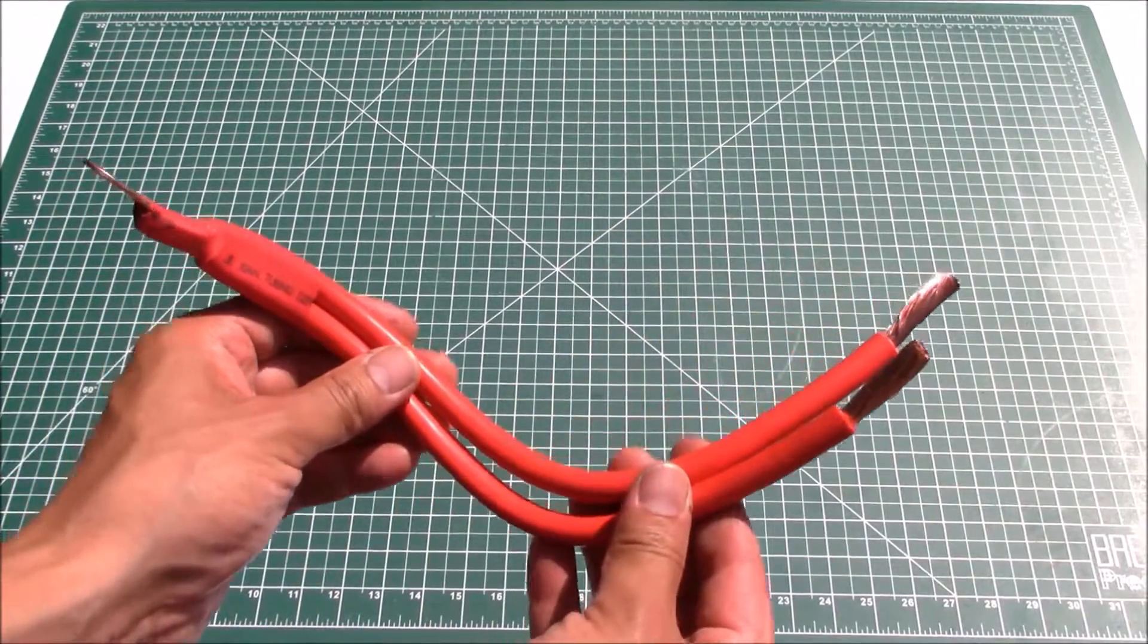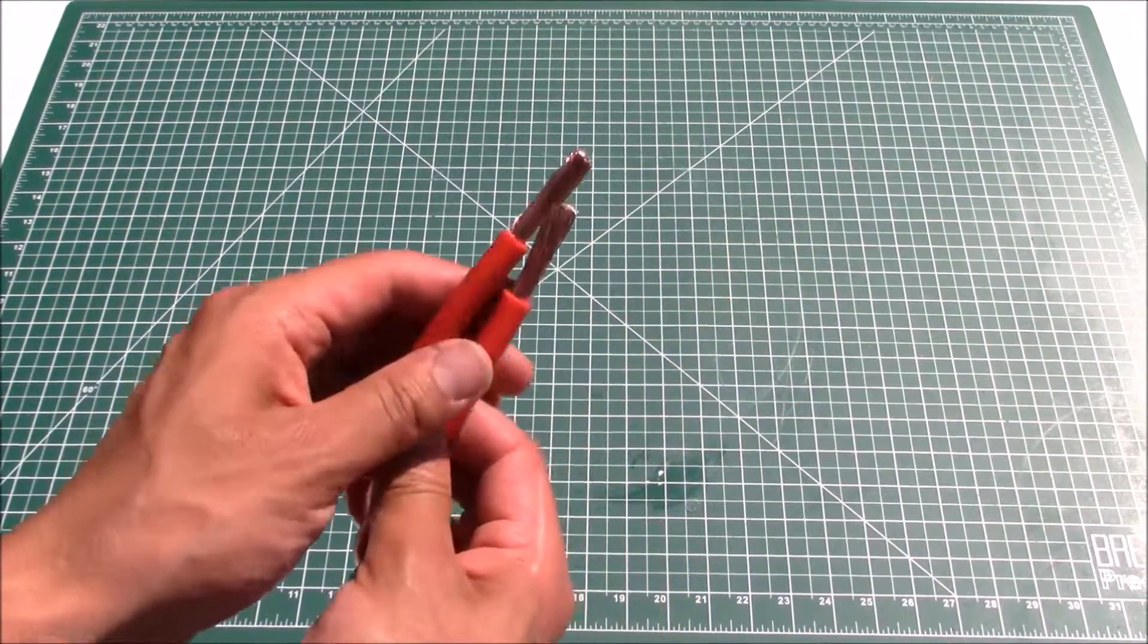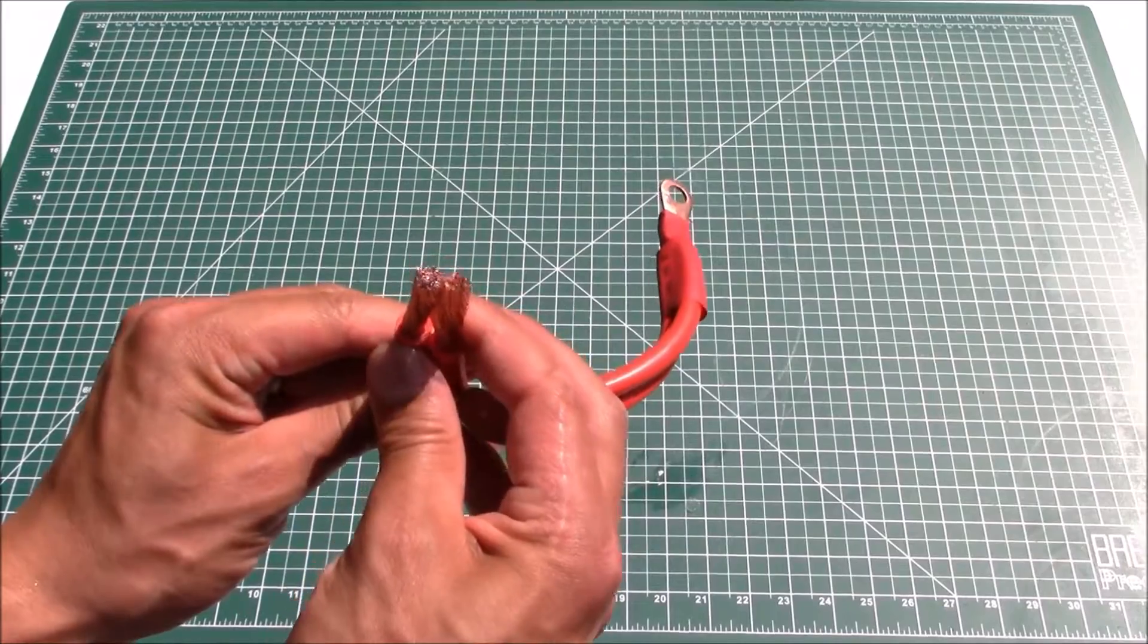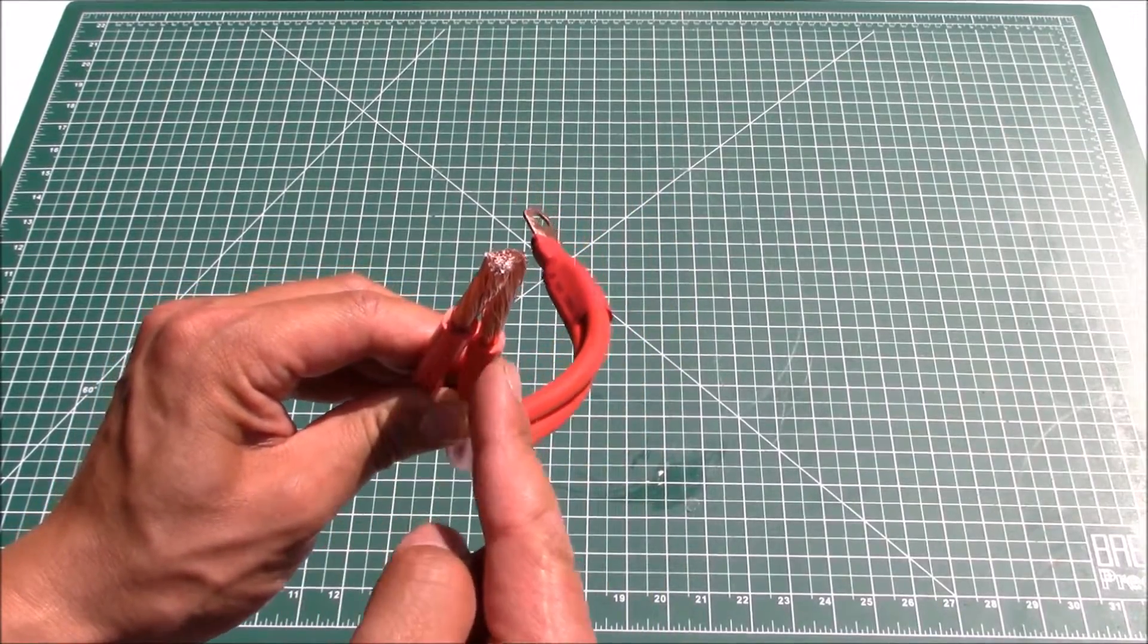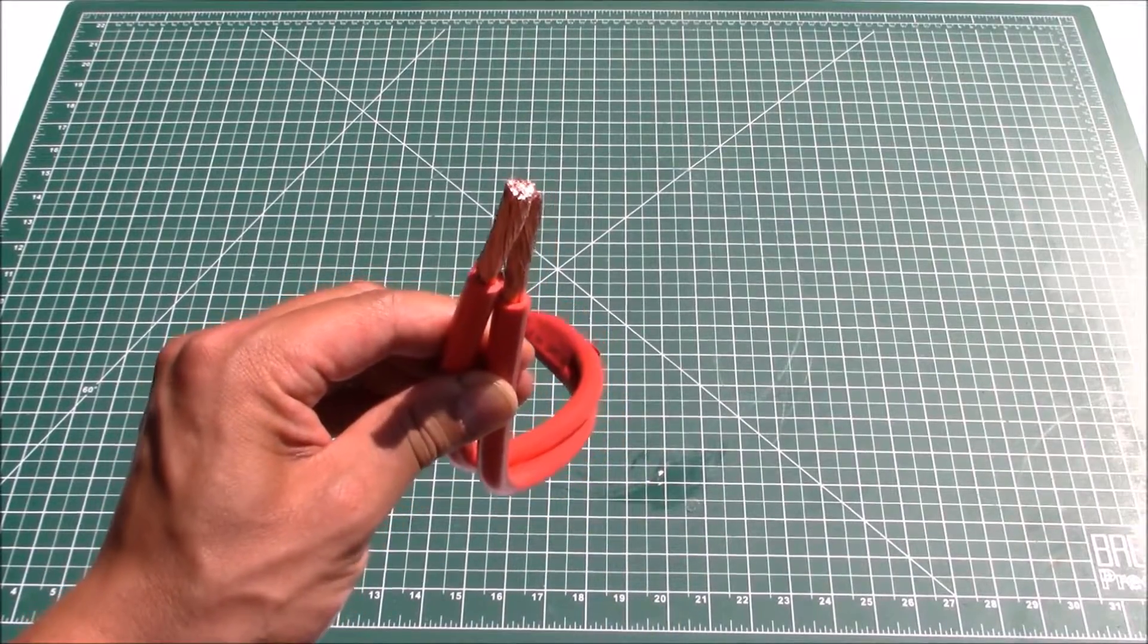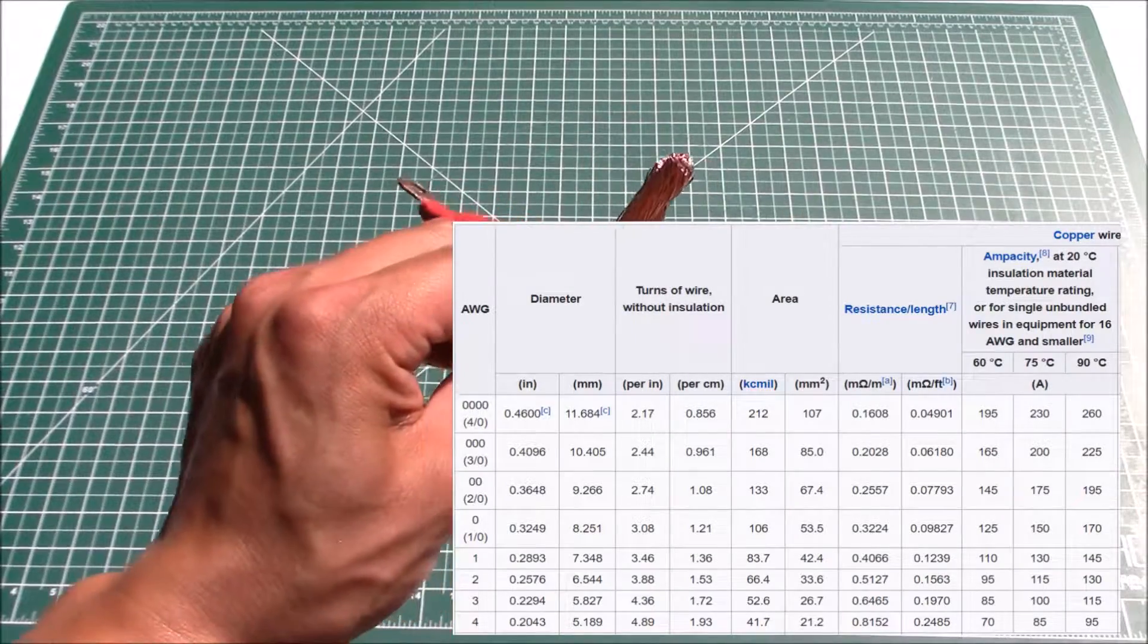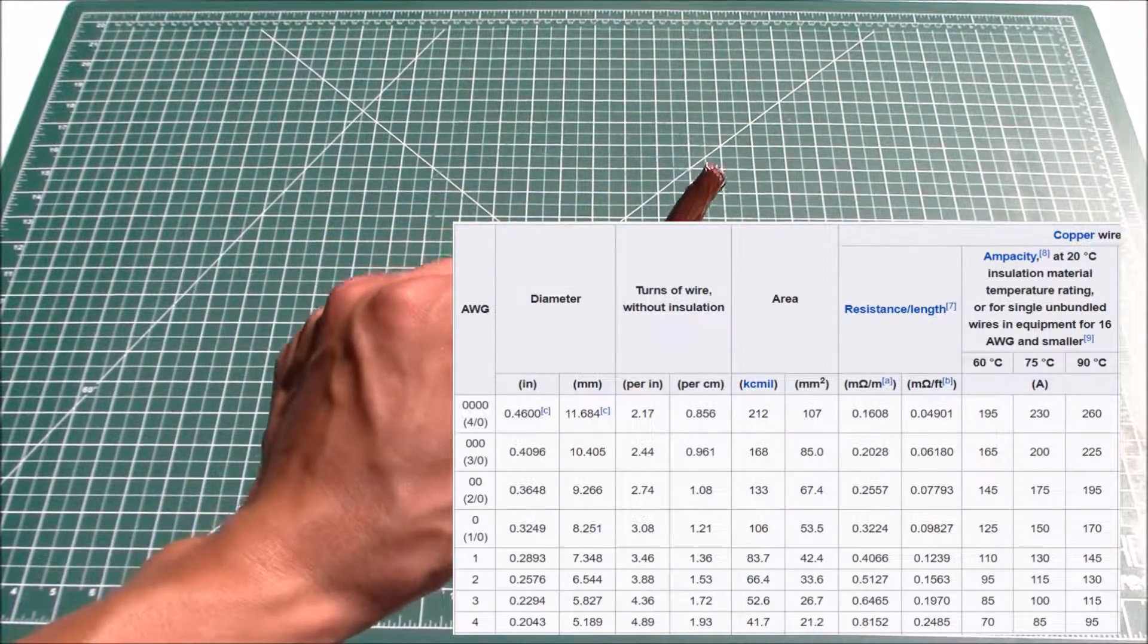The first thing we need to do is identify the nominal cross-sectional area of the cable. Since I've got two of these, you can see the amount of cross-sectional area of these two four gauge wires put together. I did the calculation - it's about 0.0656 inches squared, which is about the same cross-sectional area as a one gauge wire.